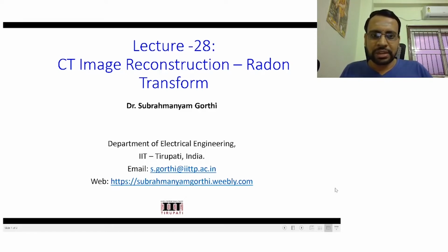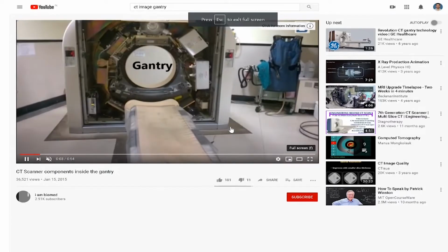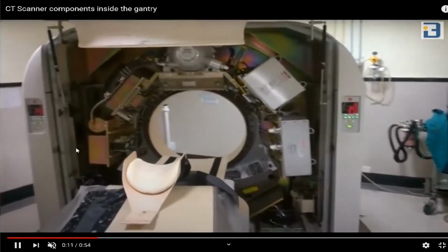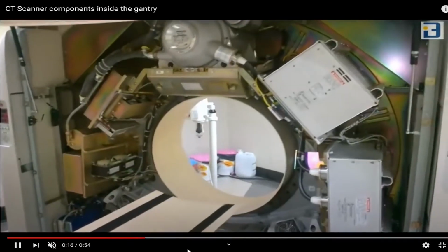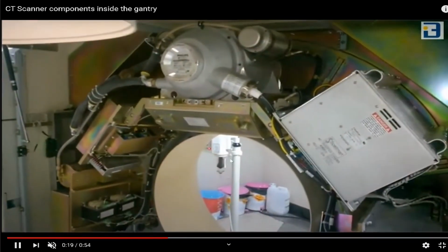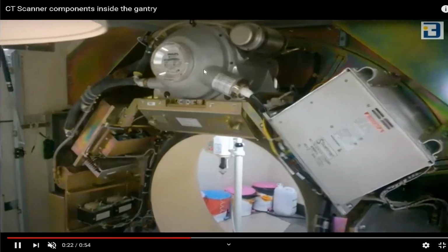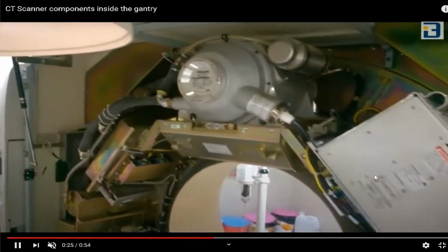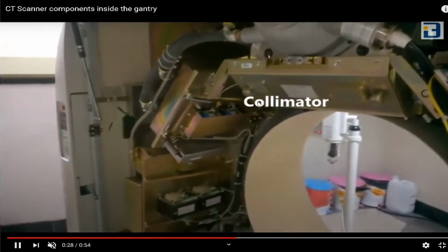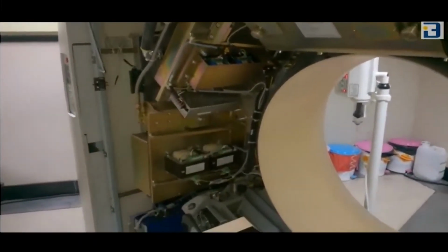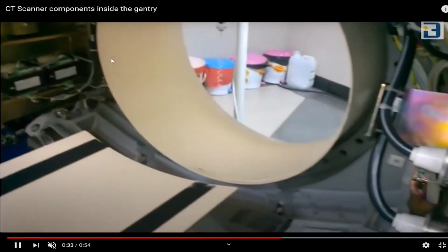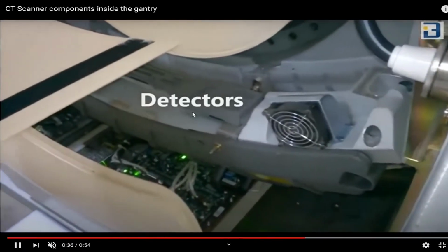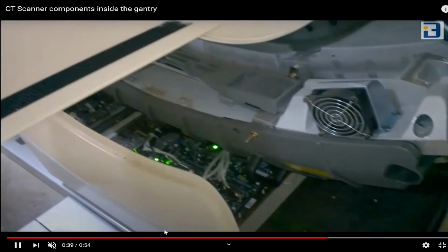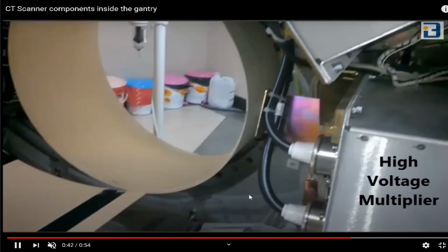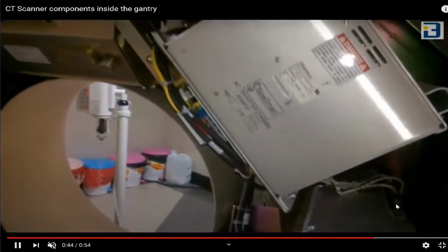What I'll do is quickly show you how the setup for a CT scan would be. I'm taking a few YouTube videos. So this is how the inside of a CT scanner would look if you remove the cover. Whatever you are seeing on the top, you have an X-ray tube for generation of X-rays, an inverter to give you the required power supply, and a collimator for focusing the X-ray beams, right? And exactly opposite to your X-ray source, you have a detector. Of course, a data detection system would be there inside it, and a high voltage multiplier for generation of X-rays.